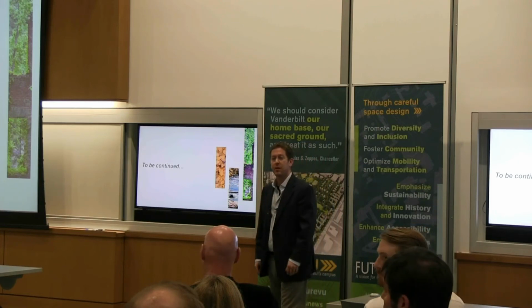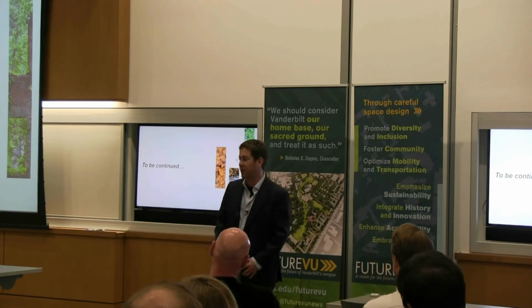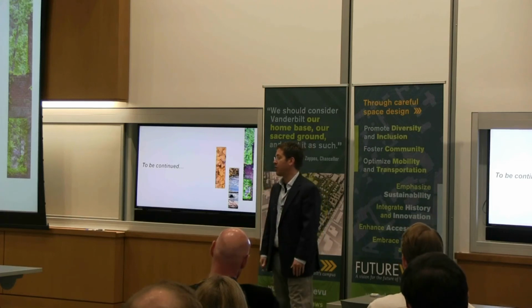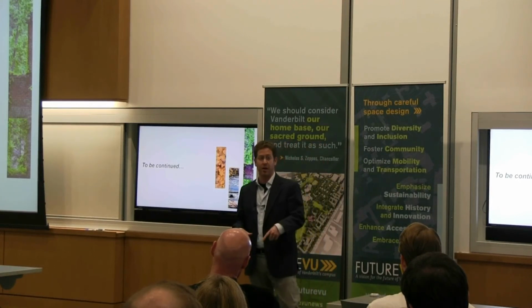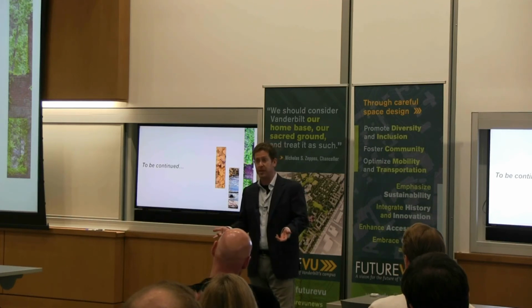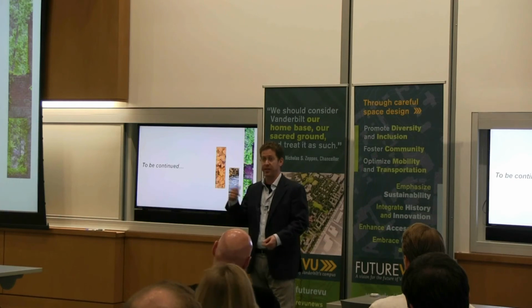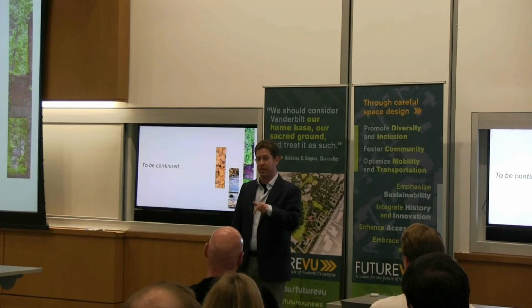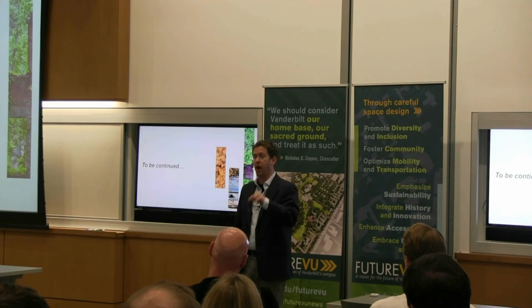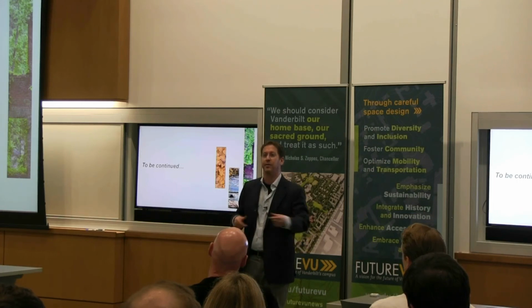So, yeah? Could you talk a little bit about who actually controls those Venetian blinds and how they control the power? Yeah, sure. So the question was, how are the Venetian blinds controlled and who really takes charge of them? The answer is the BMS. So the building's automated system includes a weather station, and so that includes wind speed. So they automatically retract above certain wind speeds, and they automatically deploy when the sun is out. And so there are light sensors as a part of that system, and so they are not manually controlled. They're completely automated, and that's part of the reason they've been successful on other projects, because they do not depend on a human to activate them, or people can't override them, etc.